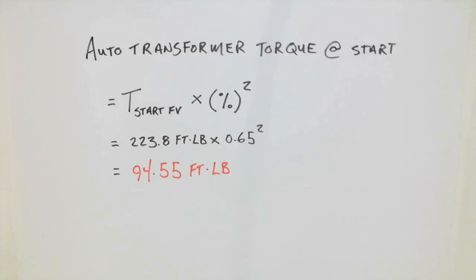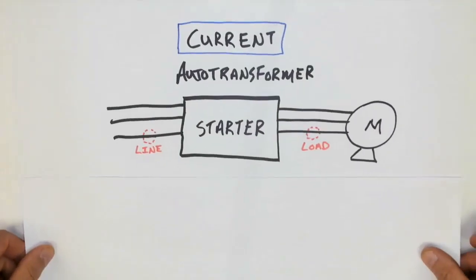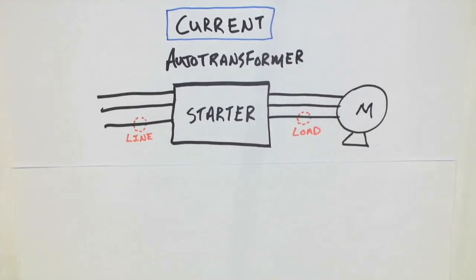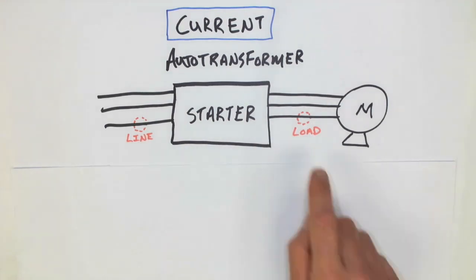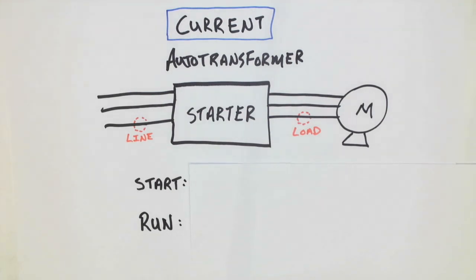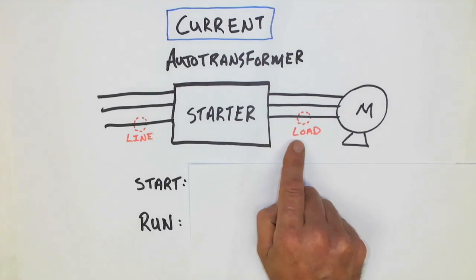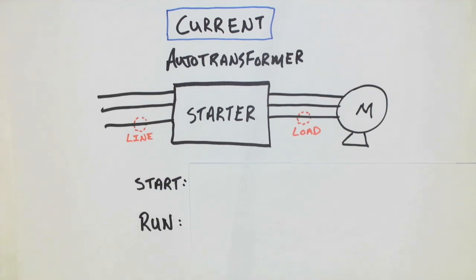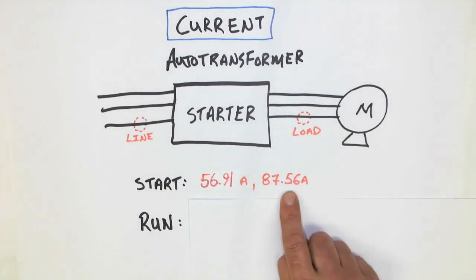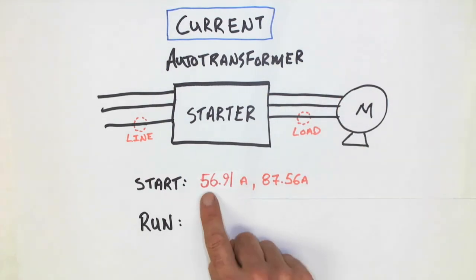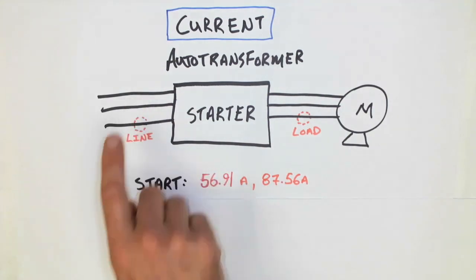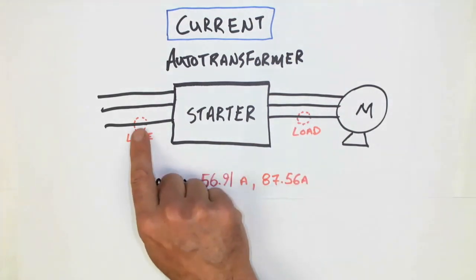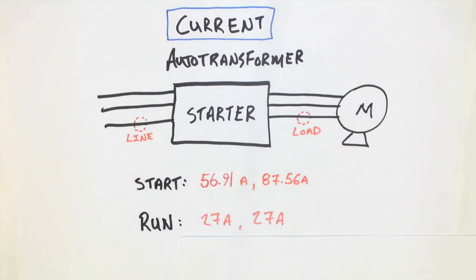Now, what about the current on both the line and the load side of this starter? We have some different things taking place due to a transformer being used, and we all know that on a transformer, the higher voltage side will render a lower current. So here we have the line and the load side. Let's take a look at start. During start, I would anticipate the load side to be higher than the line side. If we were to utilize the numbers from the previous calculation page, we would have 87.56 amps on each of these three conductors and 56.91 on each of these three conductors. So if we were measuring, we would not be expecting to get exactly the same value of current on both lines. During run, this motor is going to have a full 27 amps FLA, and it would be present on both of those sides.